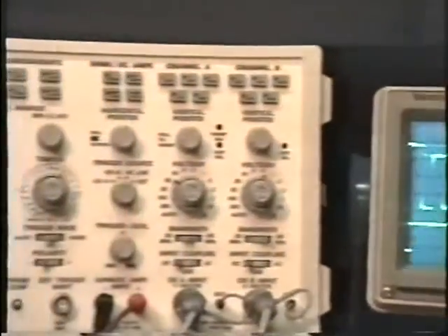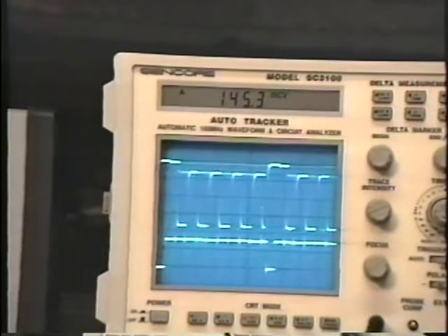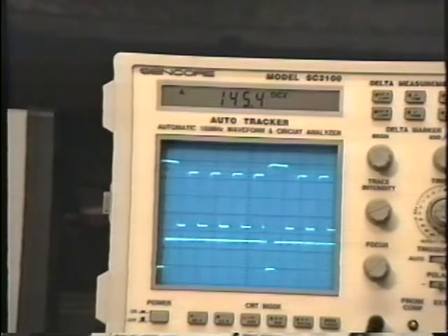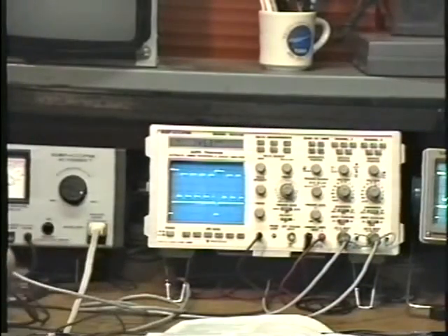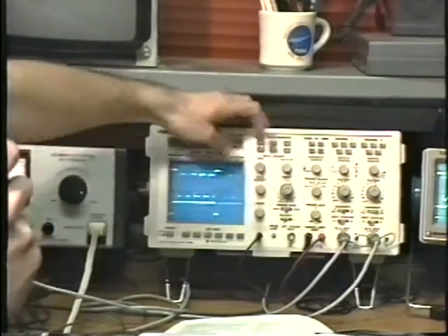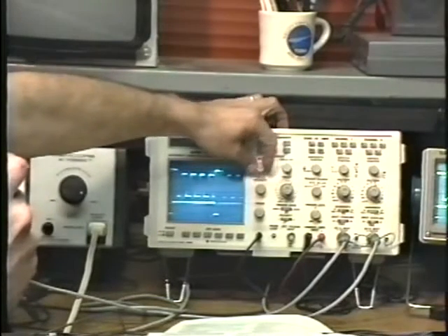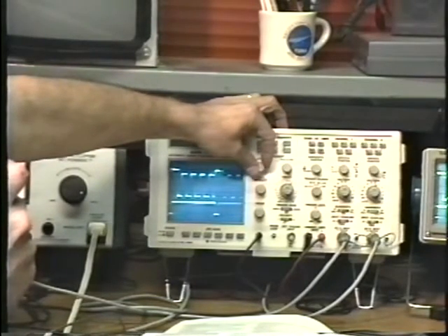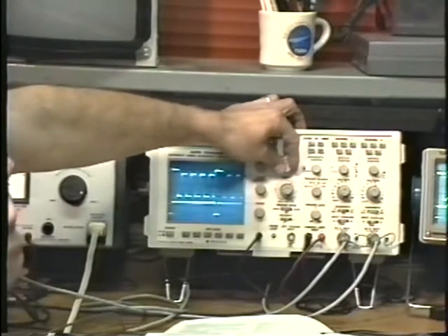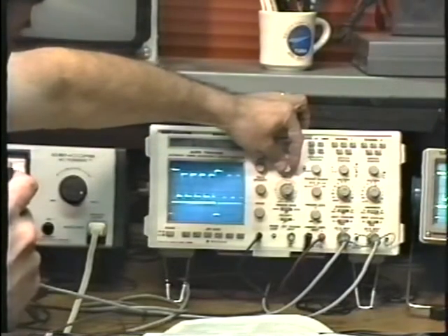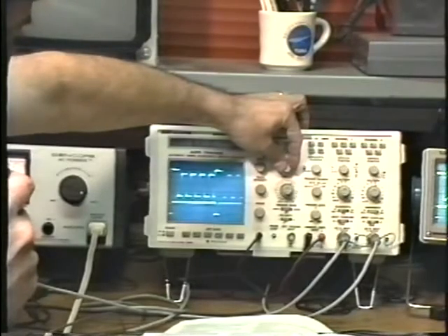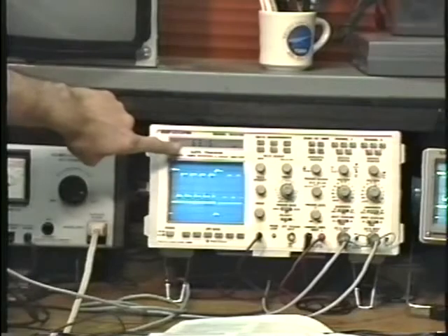Now what I really want to show you is this. This oscilloscope is made by a company called Sencore. It's the model SC3100. Actually, they call it a waveform analyzer because it does some fantastic things that a normal oscilloscope won't. For example, if I press the delta time measurement, I can illuminate just a small portion of this waveform. If I illuminate one of the horizontal sync pulses and illuminate the waveform to the portion of the other horizontal sync pulse that's exactly the same point on the waveform, I can measure the time period right off of the liquid crystal display.